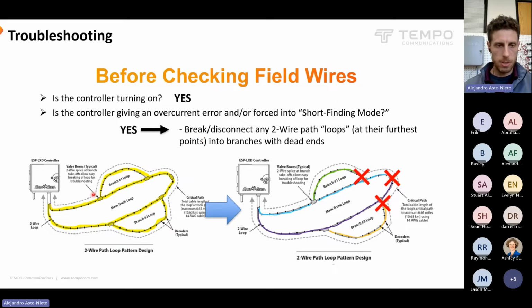So if we have this looped system here and we break the connections at the far ends of all these loops, we basically turn it into a star pattern system with branches. So we'll be able to think of everything in that system in terms of upstream and downstream now, which is helpful when taking clamp meter measurements. If you're in a loop, you're in a circle, so you can't tell what's upstream and what's downstream. So we want to be able to break the furthest points in a loop if we're troubleshooting that system.